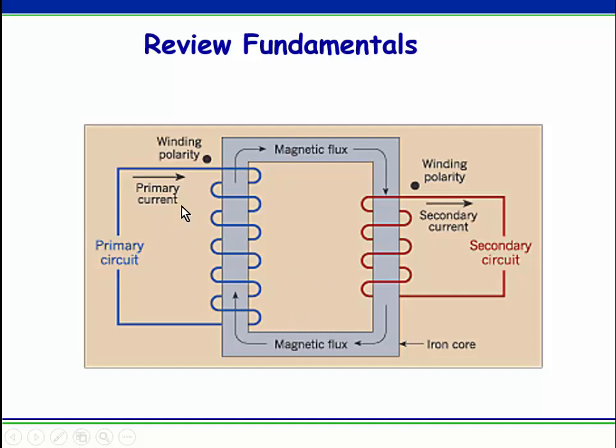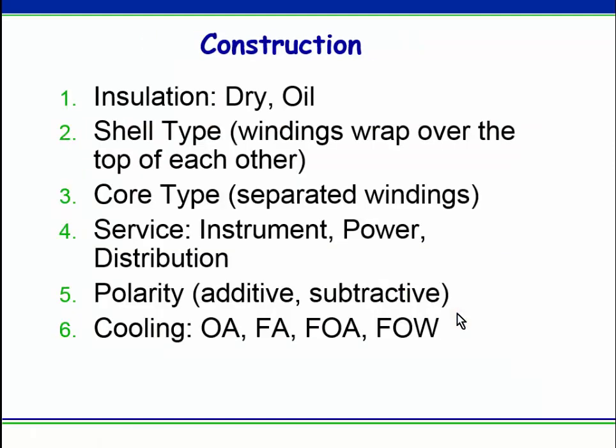Another thing is the idea of polarity. Typically on these windings, this would be H1 on the primary, and this would be X1 over here on the secondary. What that polarity means is that if they have the same polarity, when the voltage is high on the primary, it'll be instantaneously high on the secondary. If instead you have a high voltage on H1, then there'll be a low voltage down here on the sine wave. So there are different ways we can build these things. A lot of this is just for you, when you see the nameplates, to be able to understand them. I've got a nameplate or two I'll bring into class and we'll talk about them.